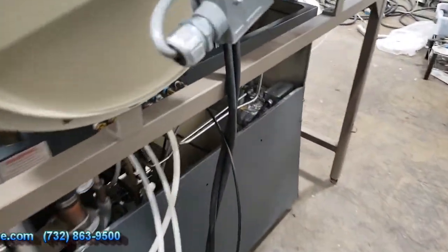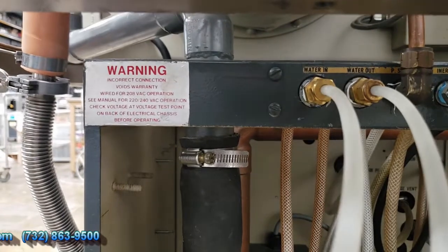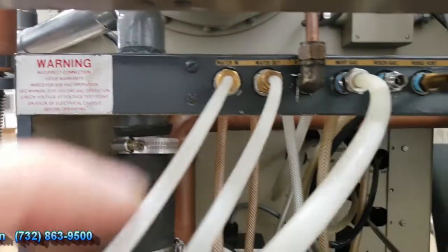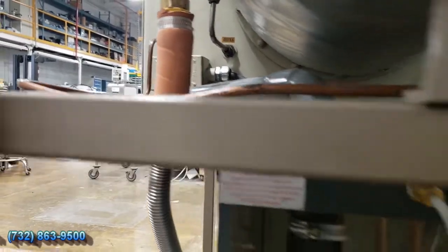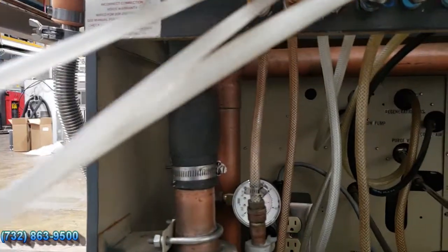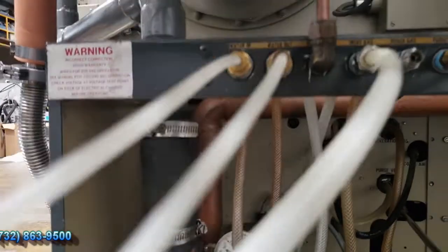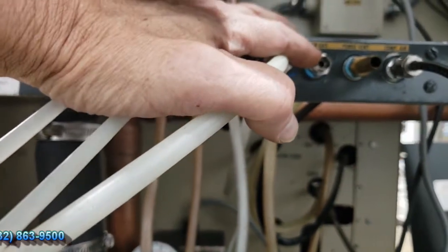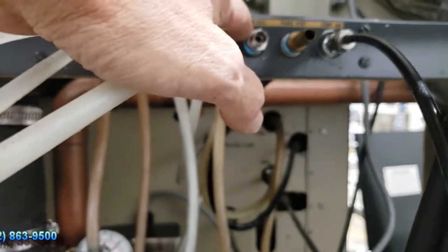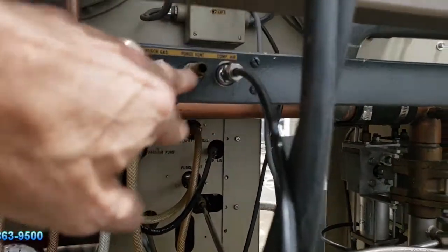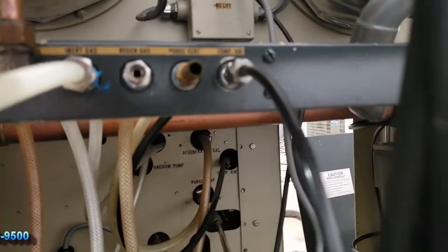Let's just go through some of those connections. You have your in and out for your water. I have about 1/4 inch Swagelok fittings there. You do have a pressure sense line here that will be disconnected when I ship it, and that'll run to your Photohelic inside to let you know what the pressure inside the box is. This is your inert gas in, coming from the tank. When you do a regen, you want to run a 1/4 inch Swagelok line in using your forming gas, and it needs to have a purge, so as you're regenerating, it's going to purge through the purifier and come out with nitrogen and water vapor. So you want to exhaust that. And then you do have a compressed air line in. I believe I have it set at 60 psi, and that's basically only used to open and close these ball valves that sit above your purifier.